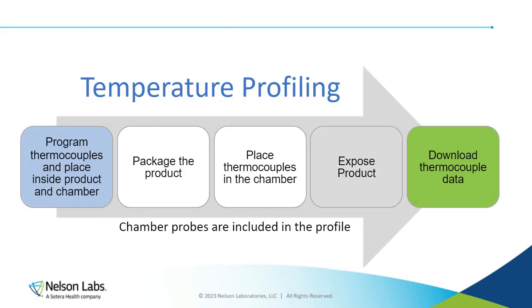Once we've demonstrated in three consecutive cycles that we can completely inactivate our BIs with the appropriate sterilization validation parameters, the next thing to consider is temperature profiling. Temperature profiling can be performed during the lethality testing or during the drying validation, though there are some concerns I'll cover. Temperature profiling is relatively straightforward: we program our thermocouples or temperature probes and place them strategically inside the product and chamber.